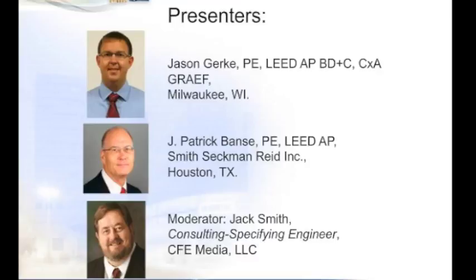That's always a nightmare when you come up against something that references the same but uses different values. First off, I'd see if it's standard 90.1 that was adopted by the AHJ or if it was the IECC codes that were adopted. And I would use the values that were in there, but then discuss it with the AHJ prior to completion of the project to determine exactly which one. But why they're different, right now I can't answer that, but sometimes that occurs.